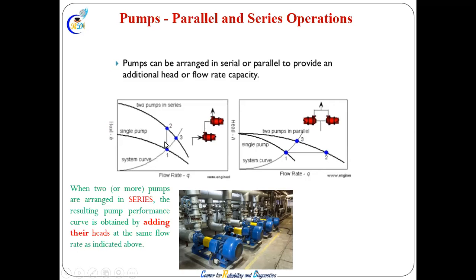So with two pumps, it is supposed to be double, but you will not get double head. You will get less head because it will come to the 3 point, since it has to encounter the system curve. So ultimately, even with more pumps, you will get the pressure only up to here, not this. This is all about parallel and series operation.